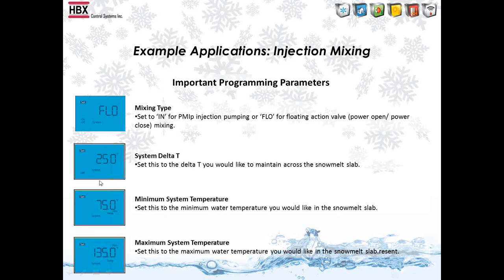So minimum system temperature. Obviously there's a minimum system temperature that you would put out to the driveway or the snow melt system, so you can set that to whatever you want. Most people set it around 70 or 75. Maximum system temperature: once you start getting over 135 degrees in concrete, you can start hurting the concrete. So 135 is about the maximum you would want to put out to a snow melt system, but once again it's based on the delta T. In this case, if the return temperature was coming back at 50, we would be outputting 75. If the return temperature was coming back at 100, we would be outputting 125. So it will go based on that delta T, so it doesn't crack the slab and it warms up accordingly.